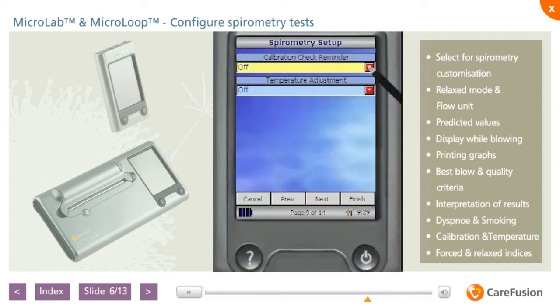Both the Microlab and MicroLoop use the CareFusion digital volume turbine transducer. The turbine is extremely stable and is unaffected by external influences such as altitude, temperature, or humidity. Recalibration by the user isn't recommended. However, we do recommend verification or a calibration check in keeping with the current ATS ERS 2005 guidelines on a daily basis, using a 3-litre syringe, CareFusion part number 36 SM2125. The calibration reminder can be set to off or daily to prompt the user to perform the calibration check prior to using the device.